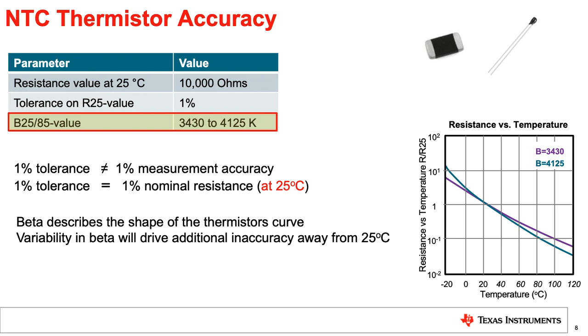Another consideration from the NTC's data sheet that must be accounted for is the variability in the thermistor's curvature. This is described in the data sheet as the beta tolerance between two temperature points. As seen on the chart on the right, the variability can have significant impact on the measured resistance as the temperature moves further away from 25C.